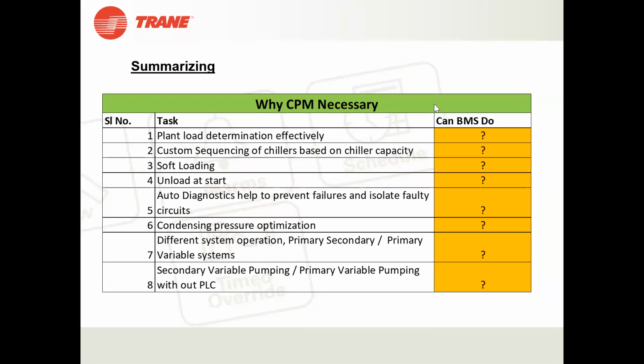Does the CPM optimize the system as per reset chilled water set point and maximize chilled water delta T? Yes, with the artificial intelligence built into the chiller plant manager system, it does perform this optimization function. Based on this, we are proposing that there are significant energy savings available in the system. There's a feature that, based on ambient temperature for condenser pressure optimization, takes input from the ambient temperature sensor and RH sensor to regulate the set point of the condenser inlet, and it applies the chilled water reset as well as the condenser inlet reset. With these applications, it gives maximum energy efficiency.